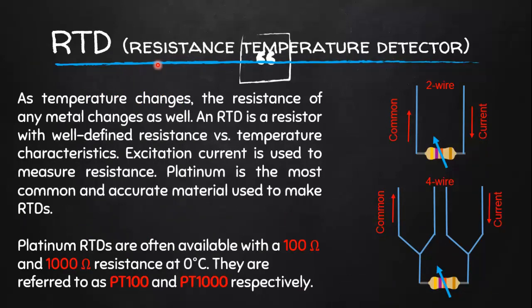Next come RTDs, or Resistance Temperature Detectors. As the temperature changes, the resistance of any metal changes as well. An RTD is a resistor with a defined resistance versus temperature characteristic, meaning its resistance changes with temperature, and it requires an excitation current to measure the resistance. Platinum is the most common and accurate material used to make RTDs. Platinum RTDs, also known as PRTDs, are often available with 100 ohm and 1000 ohm resistance at 0°C, referred to as PT100 and PT1000 respectively.